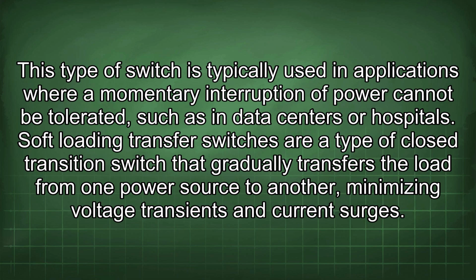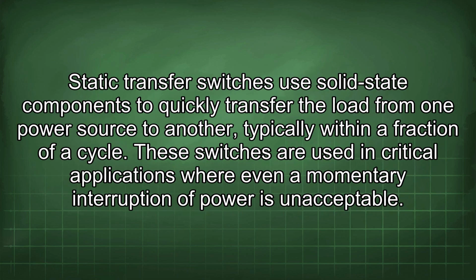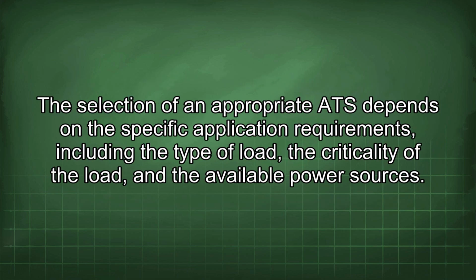Soft-loading transfer switches are a type of closed transition switch that gradually transfers the load from one power source to another, minimizing voltage transients and current surges. Static transfer switches use solid-state components to quickly transfer the load from one power source to another, typically within a fraction of a cycle. These switches are used in critical applications where even a momentary interruption of power is unacceptable. The selection of an appropriate ATS depends on the specific application requirements, including the type of load, the criticality of the load, and the available power sources.